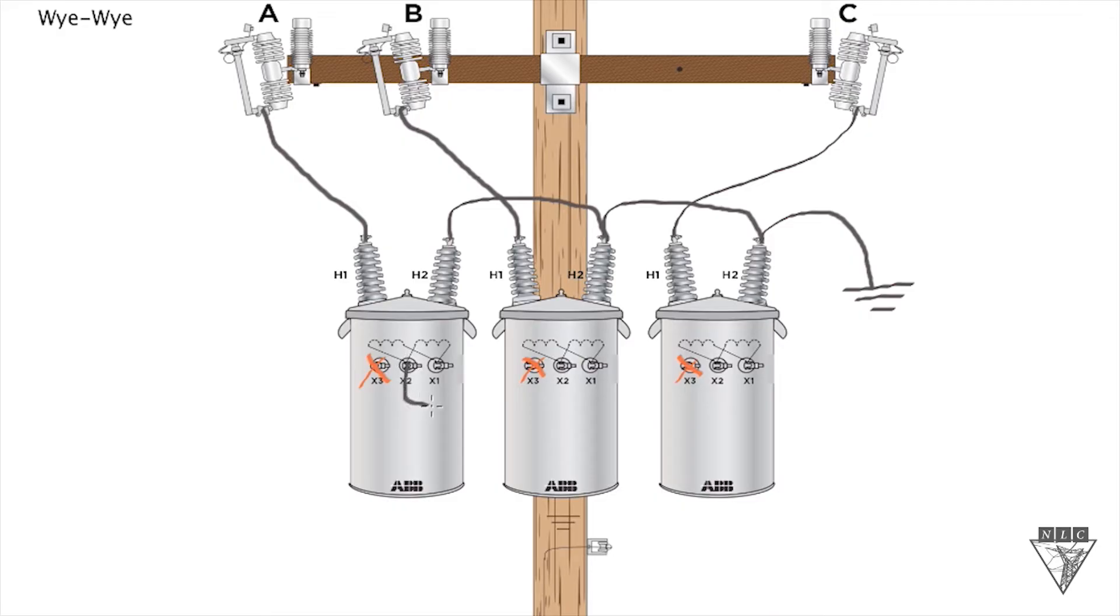So let's do the secondary connection now. The first thing we want to do is tie our X2 bushings together, make that so it's actually connected, and then tie it to ground. And that's our neutral on the secondary side. X2 bushings are all tied together and then tied to ground.